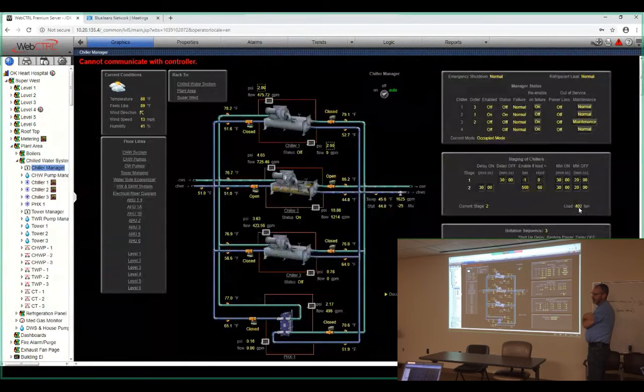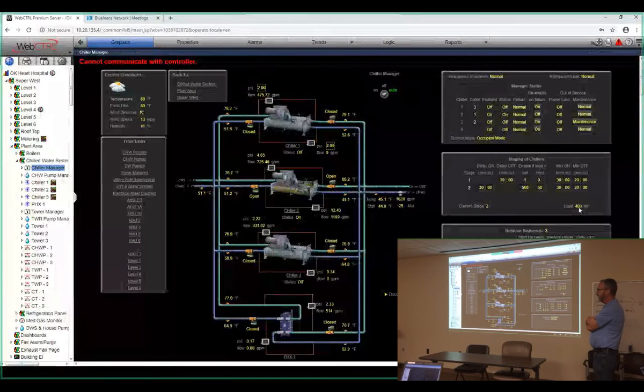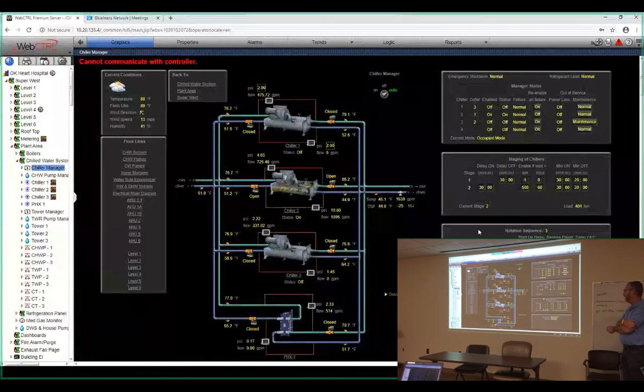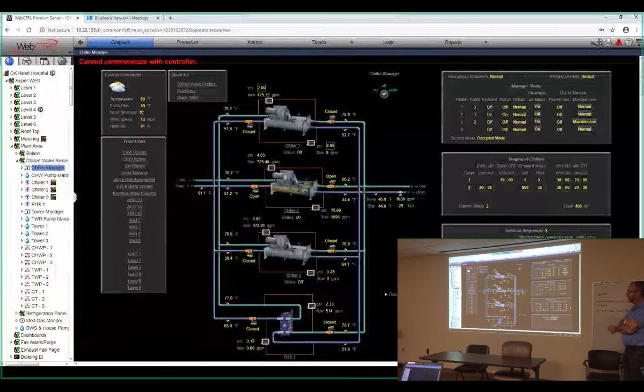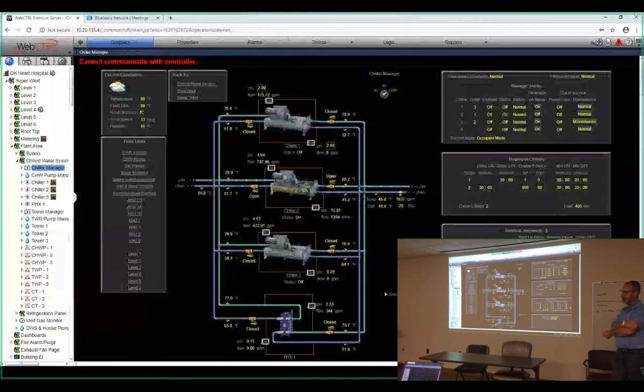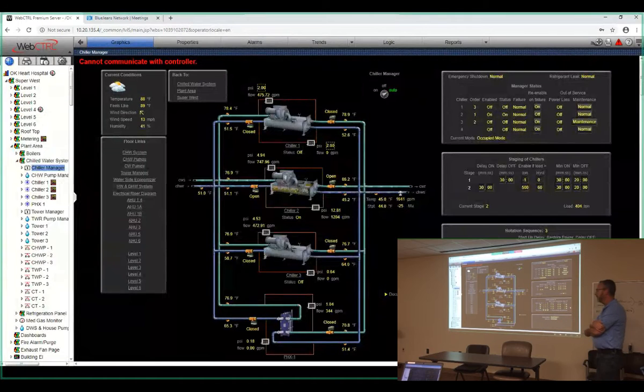The system's design was engineered to run at a lead lag with 1 standby. So we should never be running more than 2 chillers at a time. So one's in lead, the lag chiller comes on at 500 tons. Then when we rotate, we'll switch that up. And the rotation is this section here. So it can be a little confusing at first, but all of these systems run the same. So the chiller number, 1, 2, and 3, those are your chiller numbers. And then these are the order they run in. These are the 3 rotations that it can go through. So right now I'm in rotation 3. Chiller 2 is the first one to run. Chiller 3 is the second one to run. And chiller 1 would be the last one. If we had a failure, chiller 1 would come on.